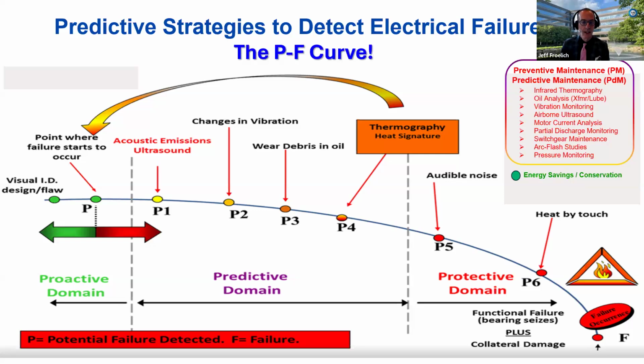It may not occur where there's a heat signature, and you may see something occurring that would be in one of the other categories. At some point, you're in that predictive domain up until that point. And then when you move beyond that, if you aren't doing thermography or aren't repairing those faults that have been identified, you start to move into the phase of audible noise. And now you're in the protective domain, getting closer and closer to failure. Depending upon temperature, the likelihood might more likely than not increase in the potential time frame where that's going to fail.